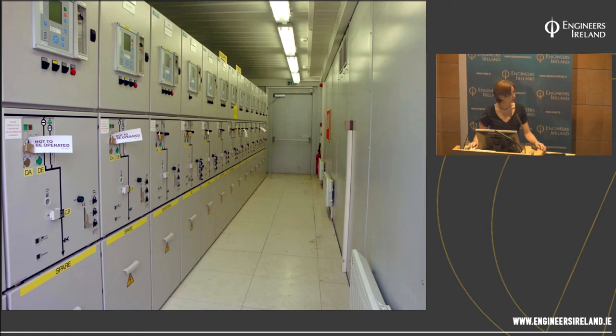And that's the picture of MV GIS in its module. Now, we had used GIS indoors before, but the switchgear that we'd used before needed rear access for HV cable termination. That wasn't going to be suitable for a module because we needed to be able to put it up against the wall. They are relatively small. So we chose switchgear with floor entry cables for termination.